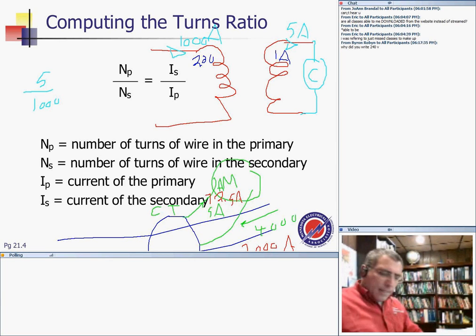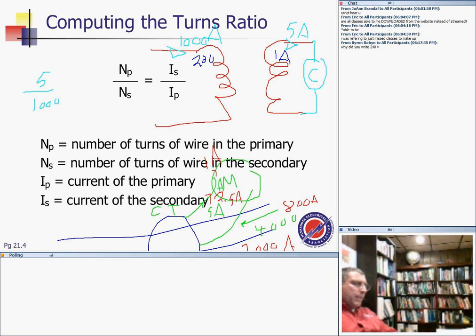Let's take the 4000. Take the 4000. This one, I'm just going to go by 5. So when you divide this, you have an 800 amp moving in here. The 800 amps in this case will be seen as 1 amp here in the system. So, guys, that's how the current transformer takes care of business.